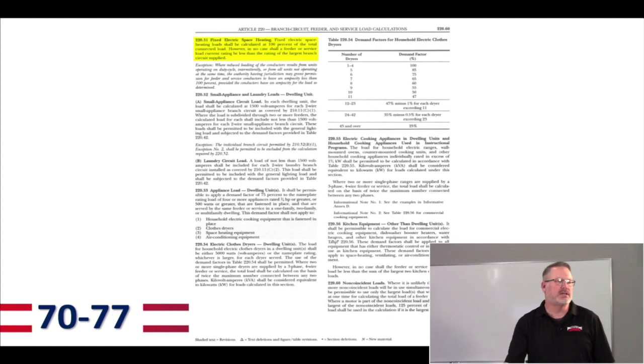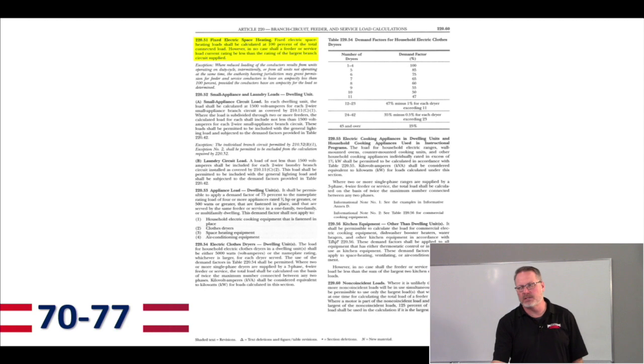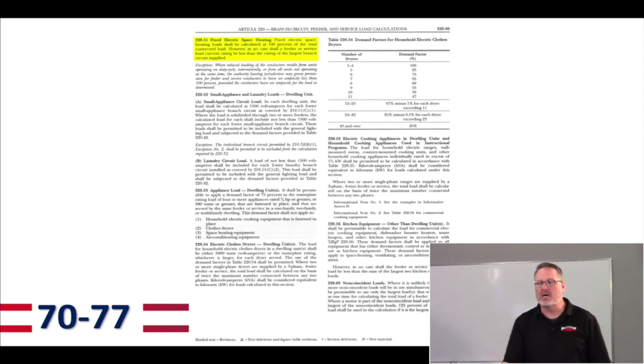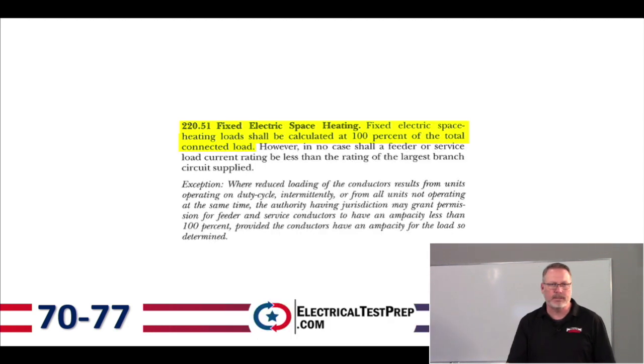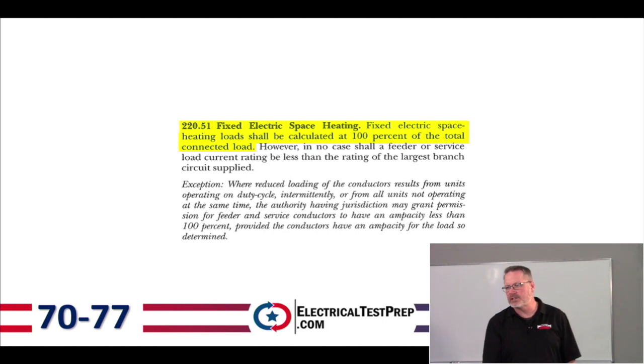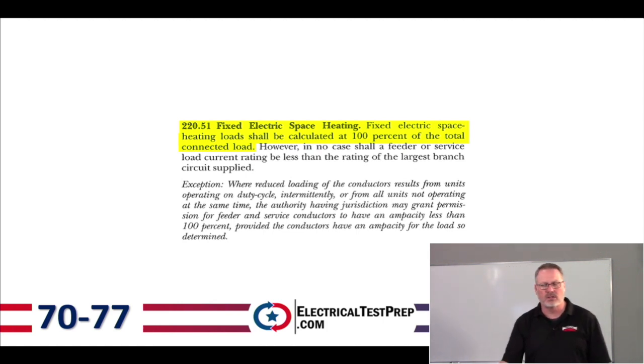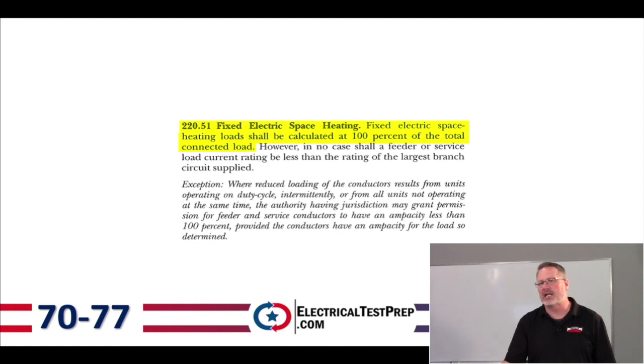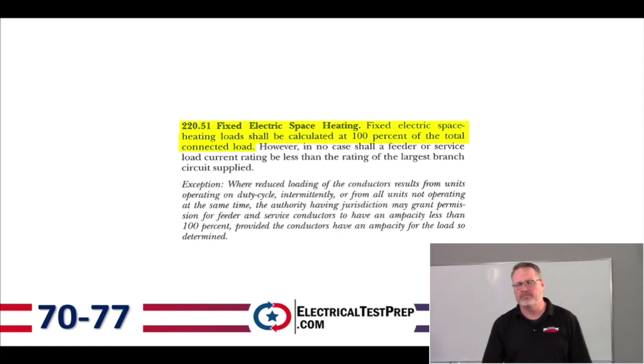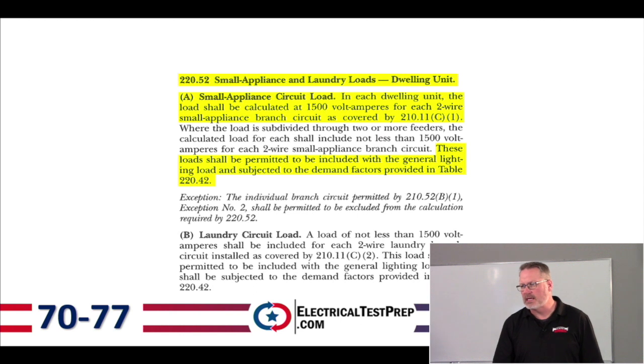Page 77, section 220.51, Fixed Electric Space Heating. Fixed electric space heating loads shall be calculated at 100% of the total connected load. So fixed electric space heating is always done at 100%.